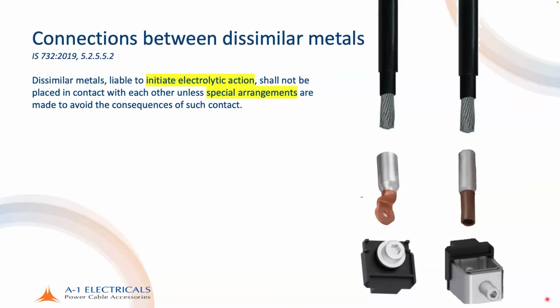Correct. Next question is from Mahesh Kumar Vasure. Which type of gland is to be used for flexible cable? If we use a PG gland, does this gland withstand short circuit current? If you have a flexible cable, it's not an armored cable, I'm assuming, then there is no need for it to withstand the short circuit current, because the short circuit current comes into the aspect of whether it is meant to form part of the protective conductor.